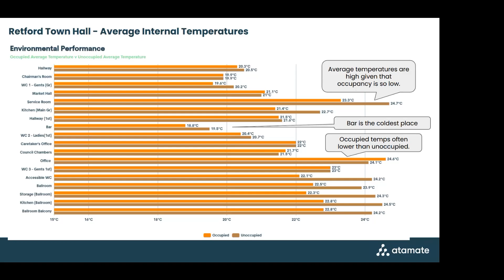So we know first of all that they're overheating it when it's unoccupied, and by going back into the occupancy level, we know the ballroom is only being used 2% of the time. So by putting some control in here, there's potential to save a lot of energy.